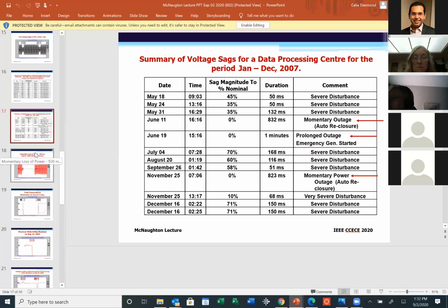This site has what we call an emergency generator that will automatically start and support the power. So that's why, for data processing centers, for control rooms, a UPS is there to support you, providing you with the power, but for a specific time, typically 10, 20 minutes. A generator can run for hours, even days, if you ensure that there is enough diesel available there. Next slide, please.